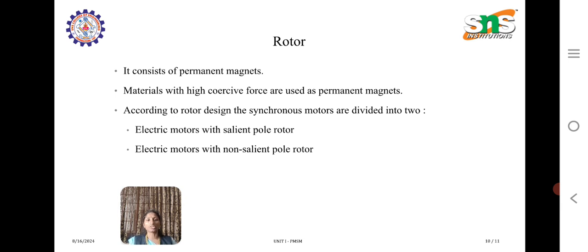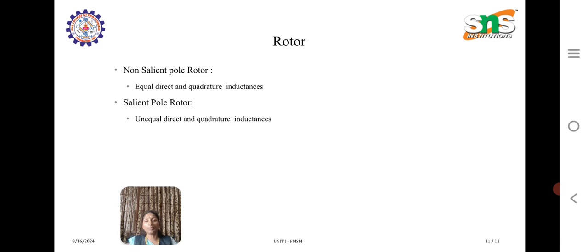Coming to the rotor, it consists of permanent magnets, and materials with high coercive force are used as permanent magnets. According to rotor design, synchronous motors are divided into two types: electric motor with salient pole rotor and electric motor with non-salient pole rotor. The non-salient pole rotor has equal direct and quadrature inductances, whereas the salient pole rotor has unequal direct and quadrature inductances.